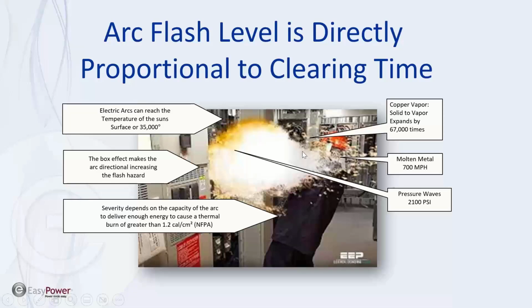But the actual ball of fire at that 35,000 degrees will go out to a certain point based on the time current curve of the breaker and the fault current. And then you have sound waves. So all of these things are dependent on the breakers not being over-dutied and being properly coordinated.